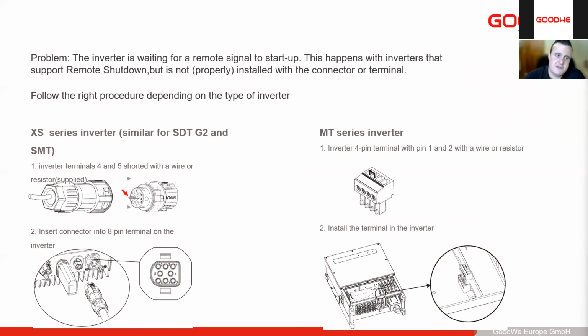Next, with the on-grid inverters, I like to sit sometimes in waiting mode. And as I explained previously, waiting mode is waiting for a condition. If our PV is correct and there's sufficient PV power to supply the load, but it's still in waiting mode, then we just need to check a few things. So our XS series, SDT G2 and SMT all have this nice connector in the blocks for the remote disconnect. We need to make sure that that is installed on the inverter, because internally there is a bridge piece which disables the remote disconnect function. So we just need to make sure that that is installed correctly and working correctly.